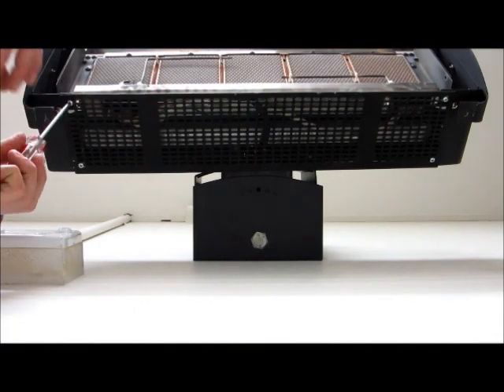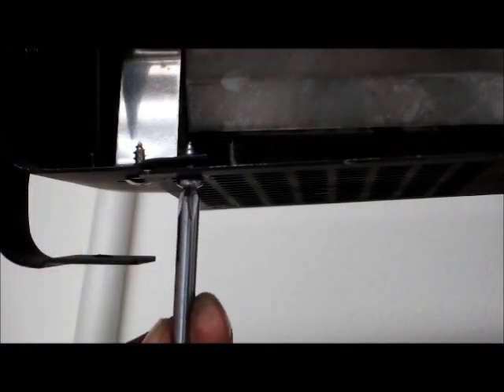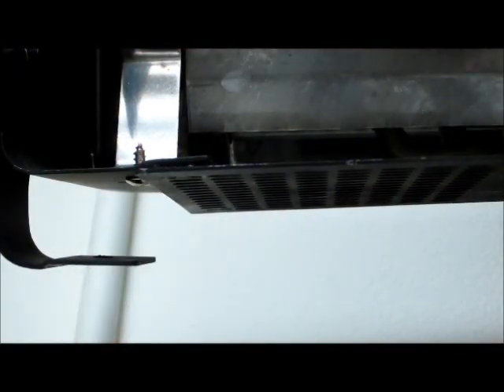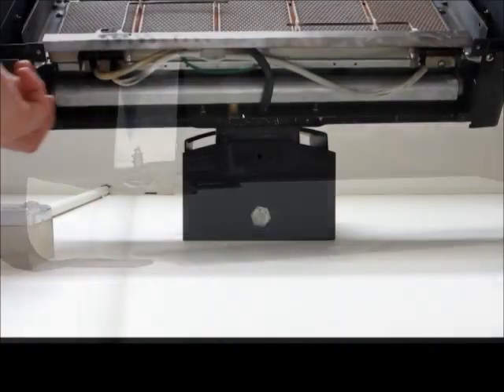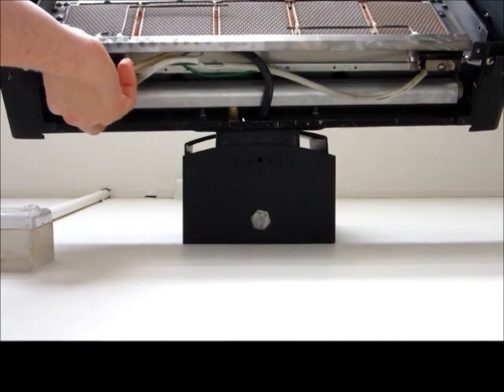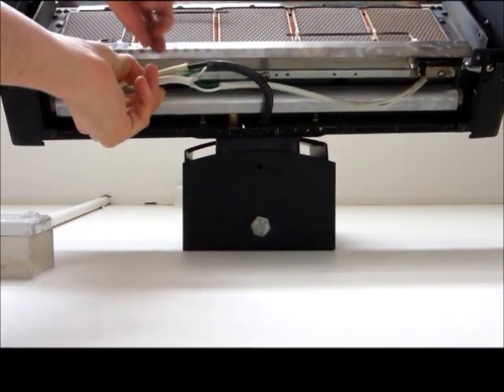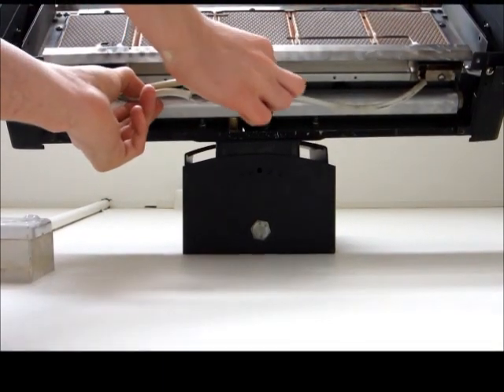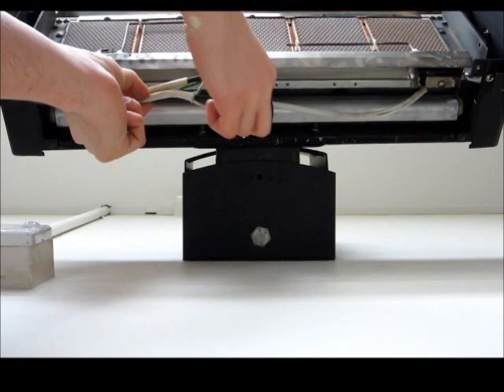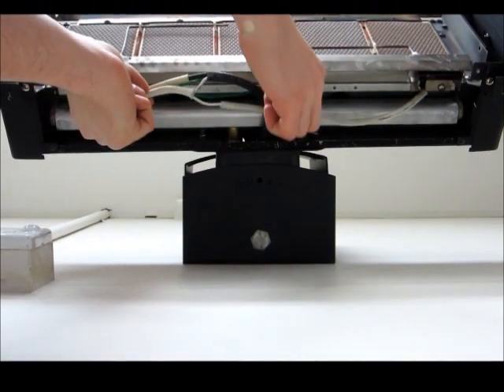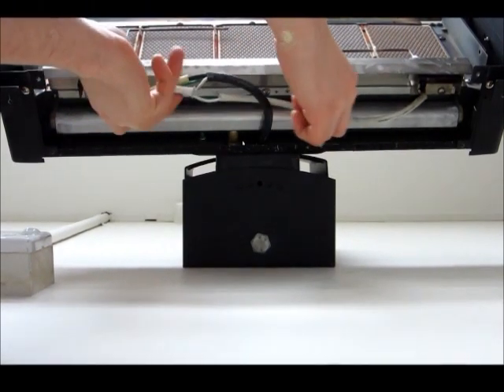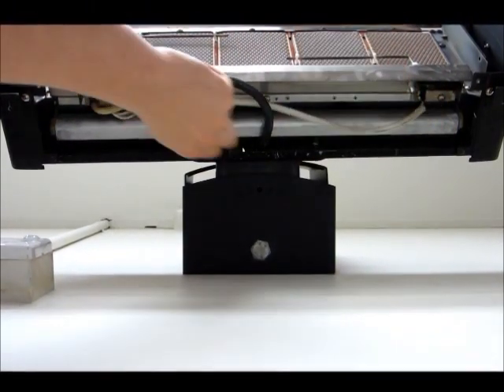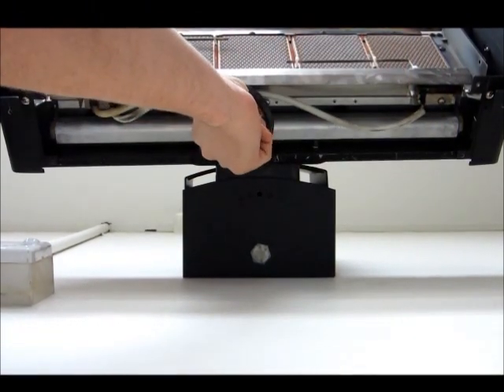Unscrew the four base cover mounting screws to remove the base cover revealing the wiring harness. Inspect the cabling to ensure that the wire insulation is complete and that there are no breaks that may be earthing out on the unit. Also ensure all terminal fittings are securely in place on the body of the heater.